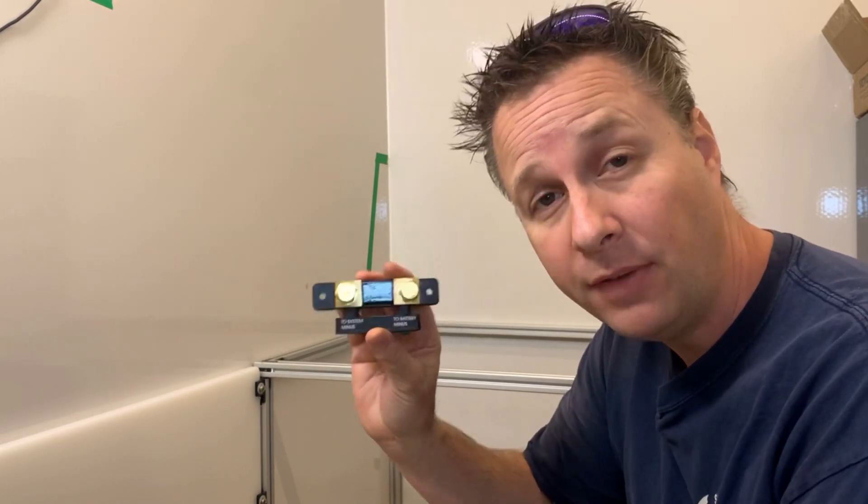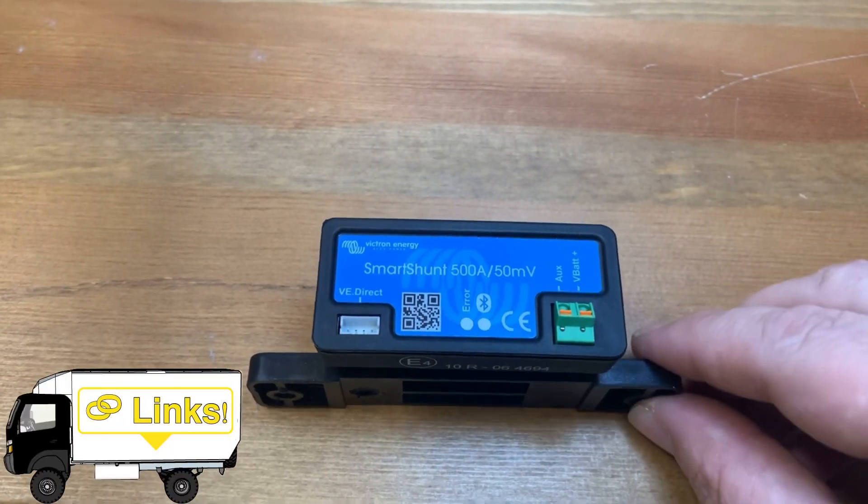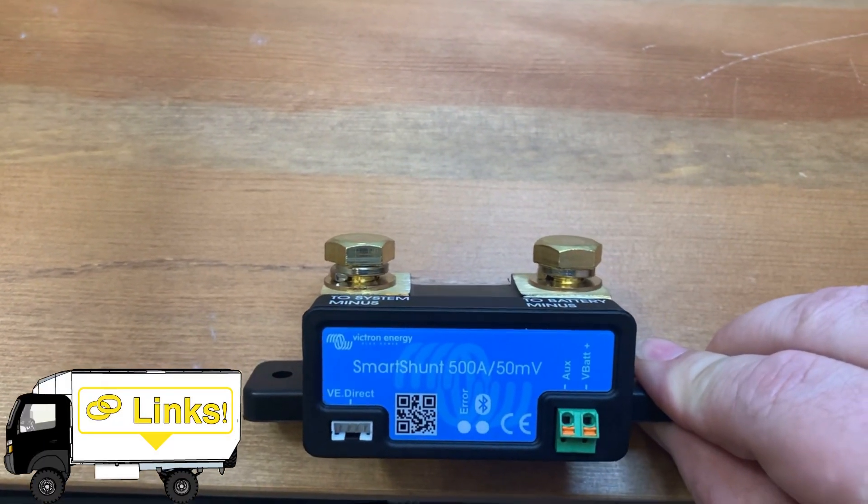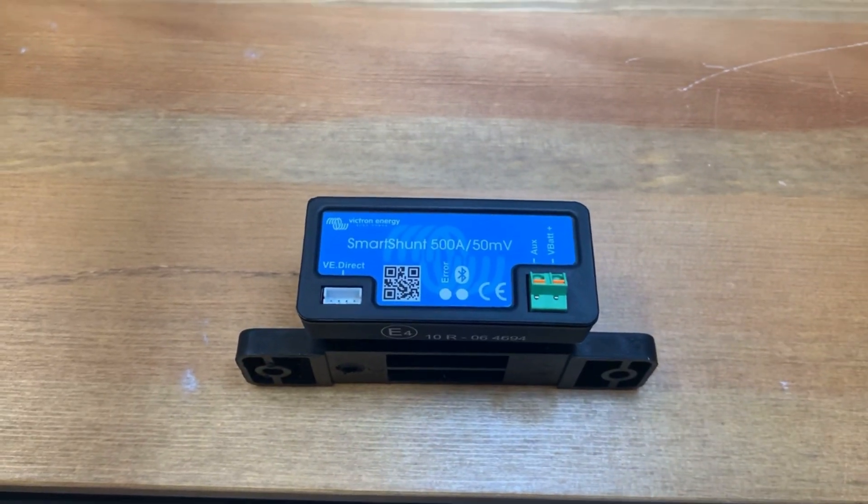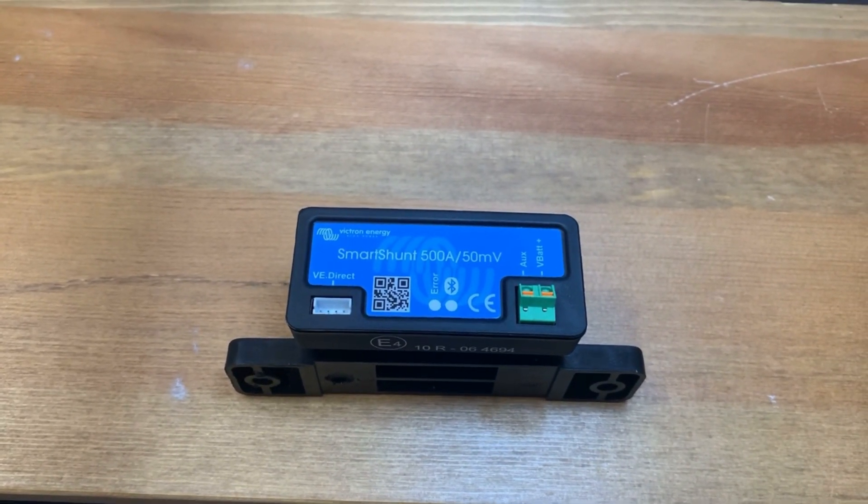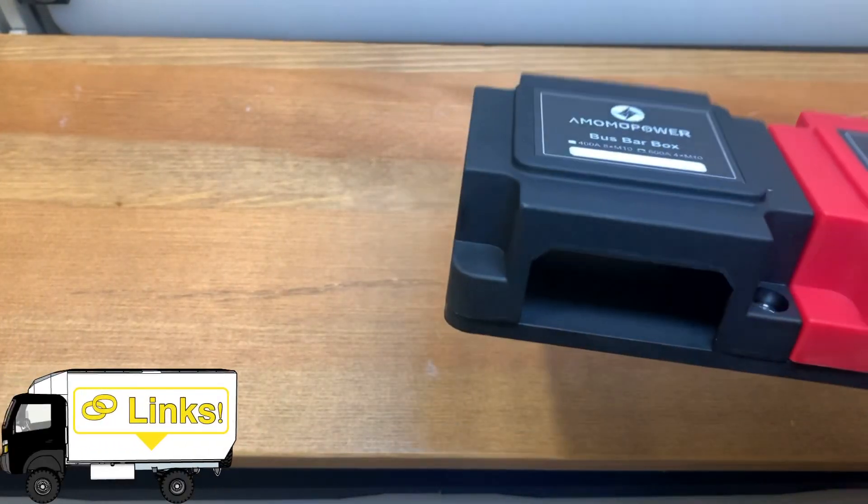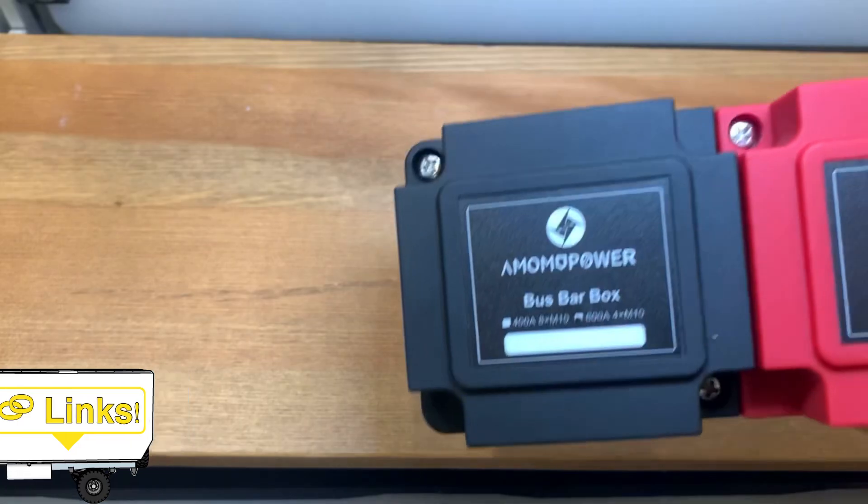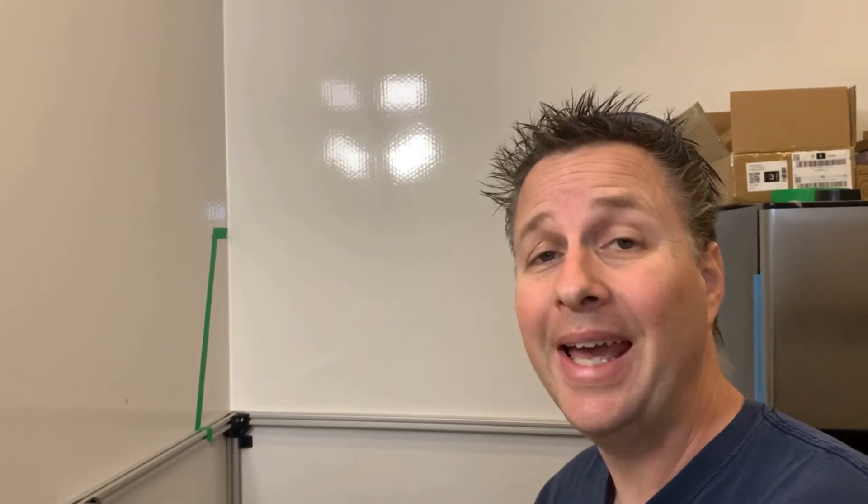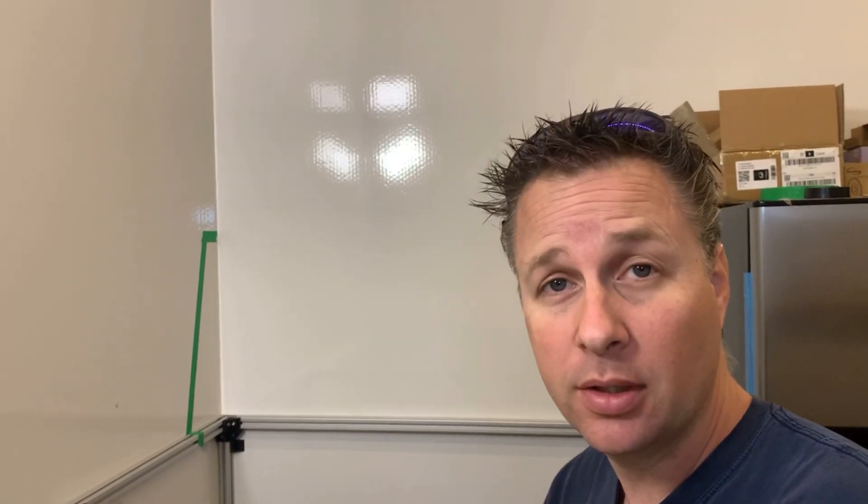All three will run to this 500 amp shunt. For those who are not familiar, a shunt is used to measure how much power is flowing through the system. This is a Victron smart shunt which means I'll be able to monitor this on my phone or an iPad or the Victron monitoring system. The output side of the shunt will then run to this 600 amp bus bar on the negative side. That bus bar will be the main connection point for any of the systems downstream.